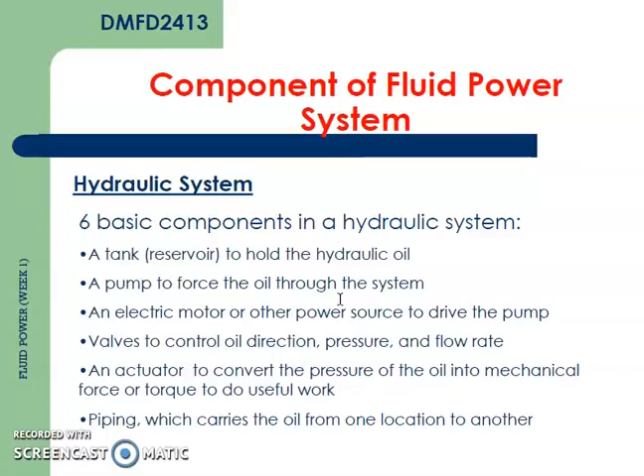There are six basic components for a fluid power system. In a hydraulic system: first, an oil tank to hold the hydraulic oil; second, a pump to force the oil into the system; third, an electrical motor or other power source to drive the pump; fourth, valves to control oil — categorized under directional control valve, pressure control valve, and flow control valve; fifth, actuators to convert pressure into mechanical force or torque; and sixth, a piping system to carry the oil from one location to another.